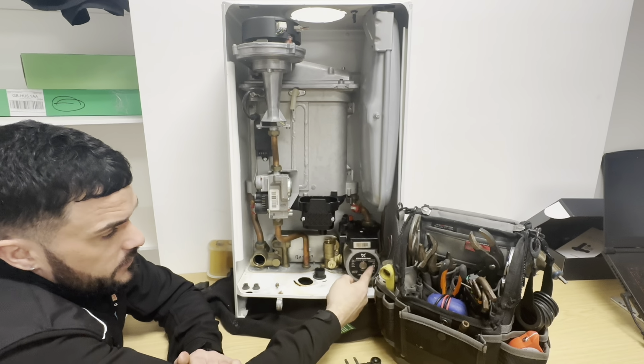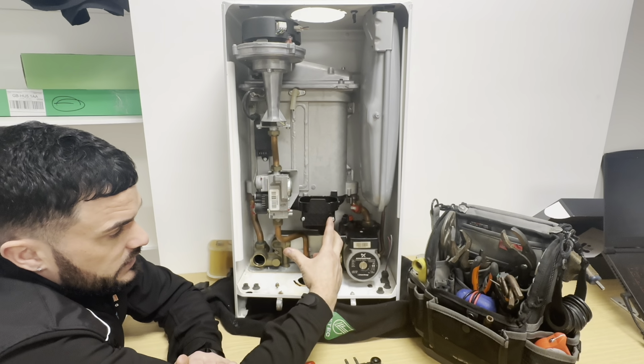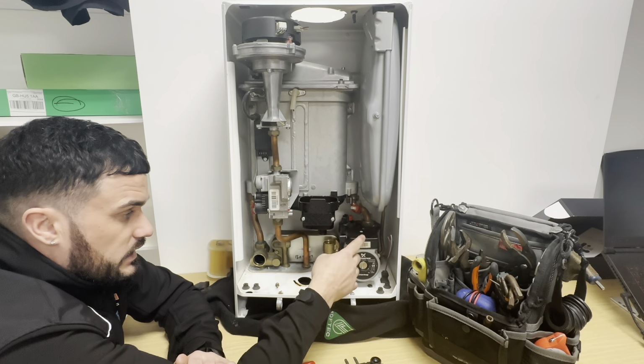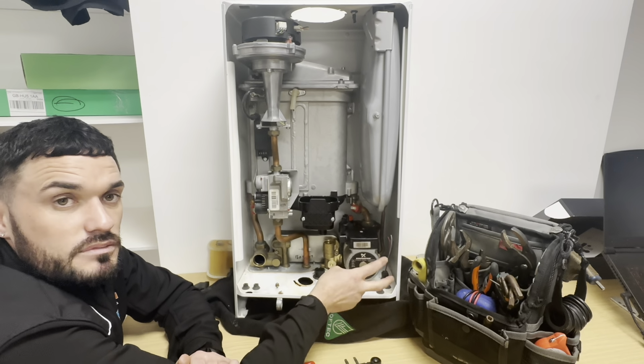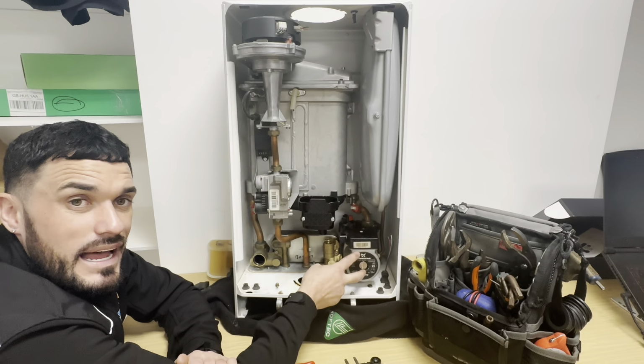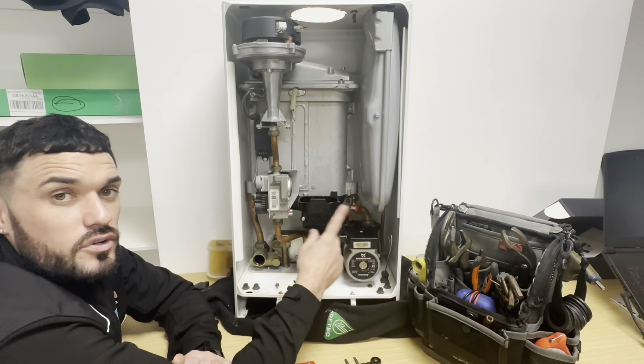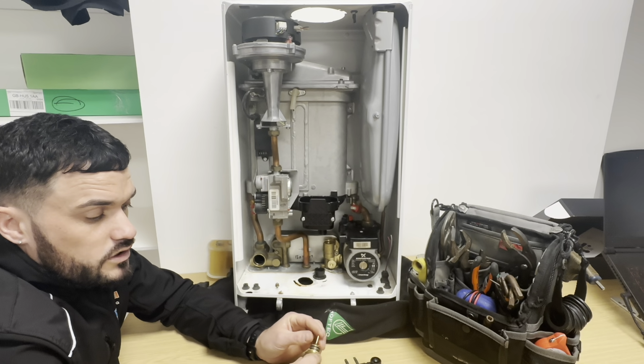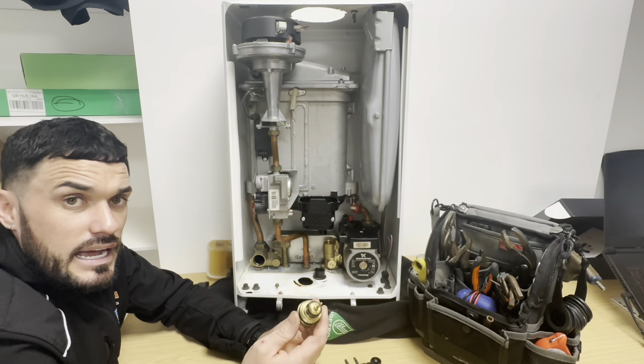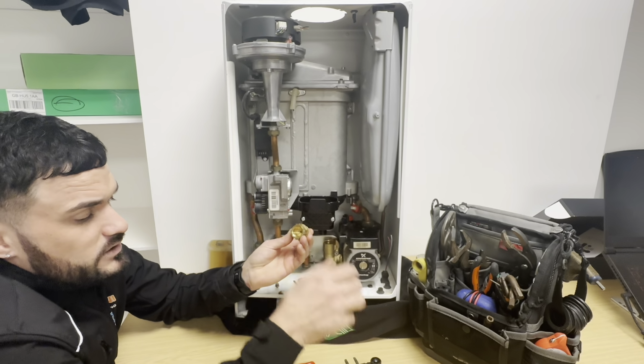Because this pump here, this 15/60 pump, what happens here is, when your system kicks in and the water comes into demand, this pump going on the heat system is great, it works fine. Once it's been sent on the plate, that has got to work a lot harder. So it's flying it on the plate. So over time, if that plate becomes blocked, it's got to get that flow on somewhere. So it can eventually push on the spring on the diverter, like I say, and then obviously end up back on the diverter.